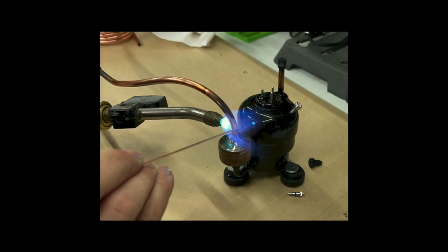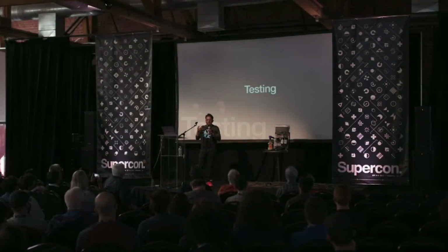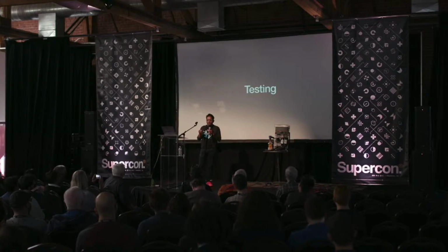Next comes testing and making sure the system is airtight. You can do that by pressurizing the system with nitrogen or other inert gas and dunking it in water - if you don't see bubbles, you're good to go. Or you can pull a vacuum and wait for several hours, making sure the pressure does not rise.